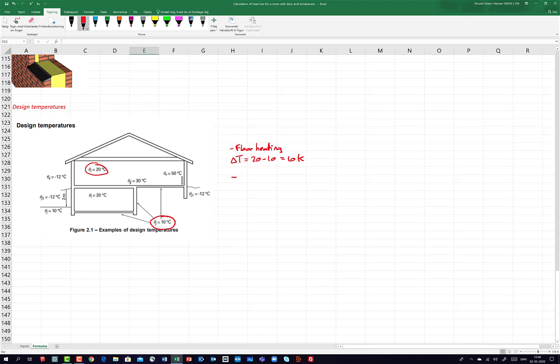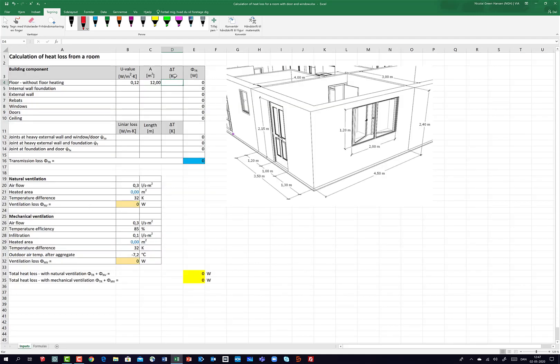If I use floor heating then it's a little bit different, because then the surface temperature of the floor should be counted as 30 degrees. In that case the temperature difference is 30 minus 10 — the soil temperature — so 20 Kelvin. But today I'll use 10 Kelvin because it's without floor heating.